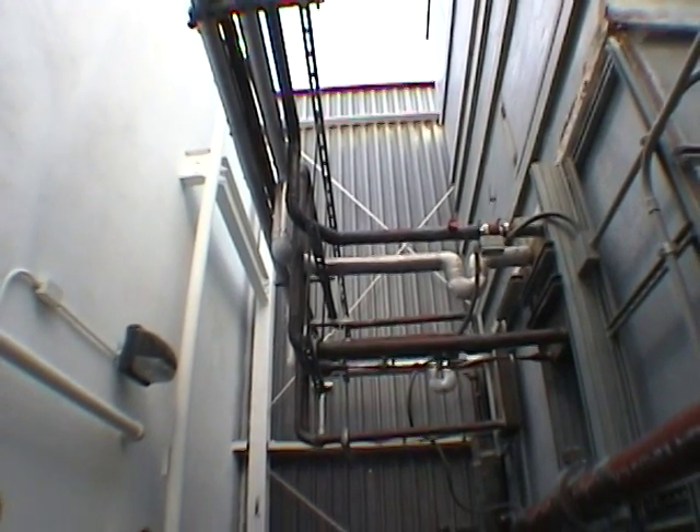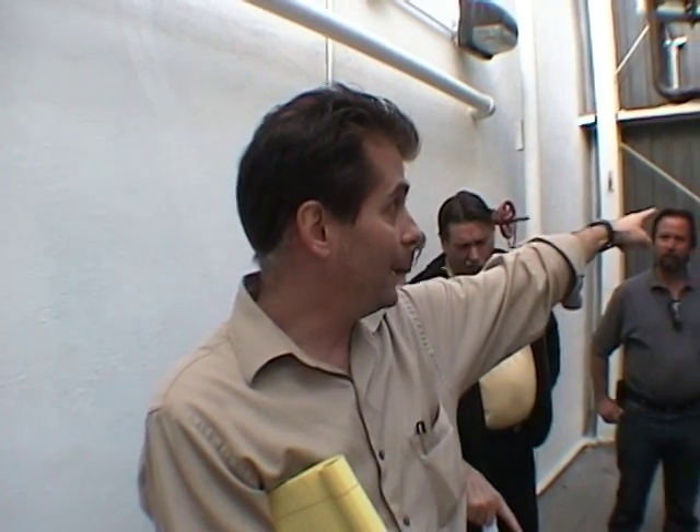If you were to ask Keith, Keith would say that should be a liquid. In the real world, that should be liquid. But there's something deficient in the design of the system, far prior to our generation, that normally that would be liquid and it would pull the liquid out of the tank. But what we discovered — we put sight glasses here. See those sight glasses? And it was flashing, which means it had bubbles in it. It had gas in it. So if we're leaving here thinking we're solid, but we're actually gassed, we've got a problem.